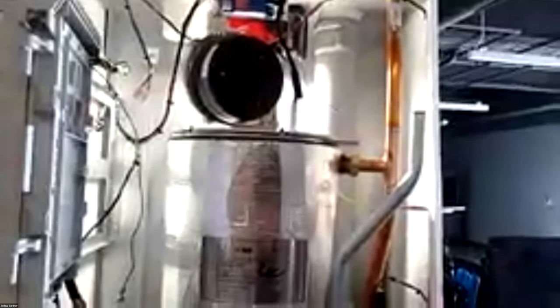So when you reinstall this too, the burner plate has an extension that goes out and attaches to the back of the boiler right here. There's one on this side and one on the other side. You don't need to reinstall those screws. This burner plate is extended out there to keep this thing nice and solid during shipping. That's all it's there for. So when you reattach this burner head, you just have to do the bolts. You don't have to do these two screws in the back where the arms reach the back. Totally don't have to do it. It doesn't affect the operation of the unit or the structural integrity of it.